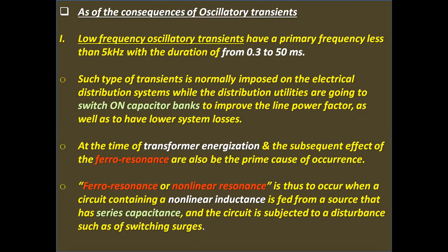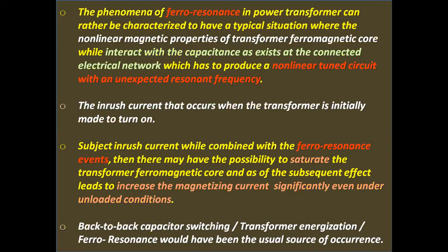Ferroresonance or nonlinear resonance is said to occur when a circuit containing a nonlinear inductance is fed from a source that has series capacitance and the circuit is subjected to a disturbance such as switching surges. The phenomenon of ferroresonance in a power transformer can be characterized as a situation where the nonlinear magnetic properties of the transformer ferromagnetic core interact with the capacitance existing in the connected electrical network, producing a nonlinear tuned circuit with an unexpected resonant frequency.